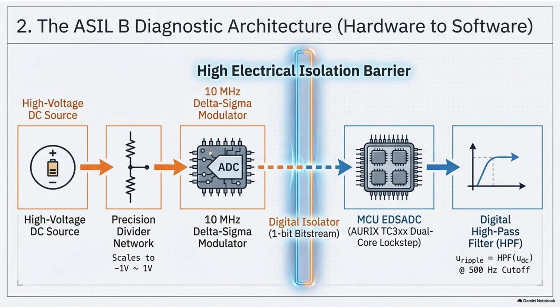Seriously. But there's a fourth and final root cause that adds brutal mechanical reality to the mix. Terminal loosening. Right. These high-voltage connections aren't soldered onto delicate circuit boards. They are heavily bolted metal joints carrying hundreds of amps. And those bolted joints are subjected to constant aggressive road vibration. I mean, you're driving over potholes, rough highways. And over time, that vibration can cause the bolts to lose a microscopic amount of their axial preload. The bolt relaxes, just a fraction of a millimeter. But when that happens, the contact impedance, the physical resistance between the two pieces of metal, jumps from microohms up to milliohms. Now, a milliohm sounds entirely insignificant to me.